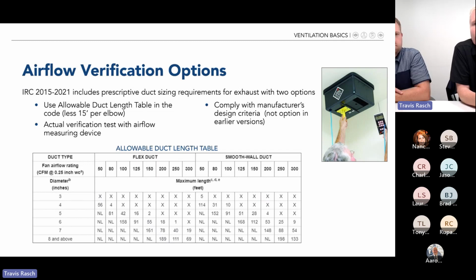So in most recent codes, ever since 2015, in the residential code, which the majority of states are on at least 2015 now, they give you 3 options to verify your airflow. One, probably the most common one, is this allowable duct length table that we're showing here. As I mentioned, the importance of 1/4 inch airflow: if you look in the upper left-hand corner of that table, you'll see the whole table is based on a fan's 1/4 inch rating. Again, we're talking about a fan or range hood here, bath fan or range hood.